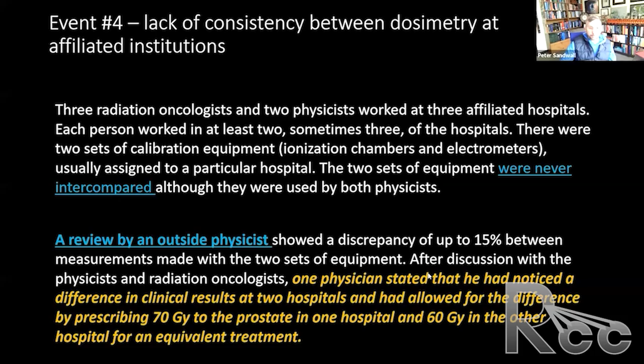But this was a system problem because he didn't share this with his colleagues, which is really unfortunate. But that incorrect calibration, where the wrong calibration factor was used, there were a lot of things contributing to this event. So there were ineffective procedures. There were different calibrations, but they were never intercompared. If you have two sets of chambers within your system, one of the first things you should do is at least see that you get reasonable results. They should be within 1% of each other.